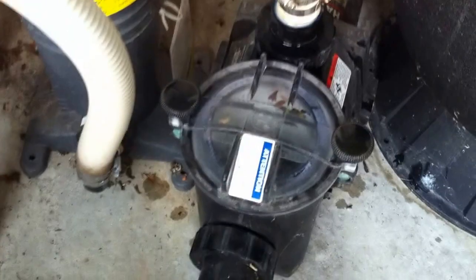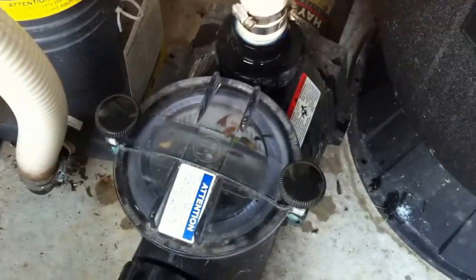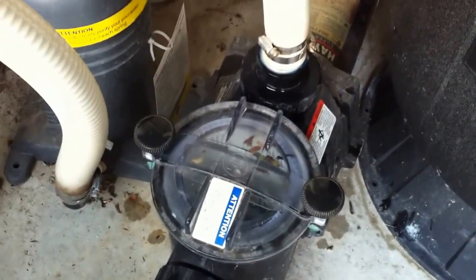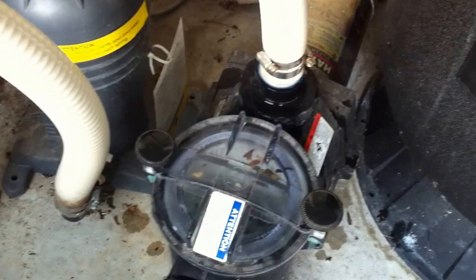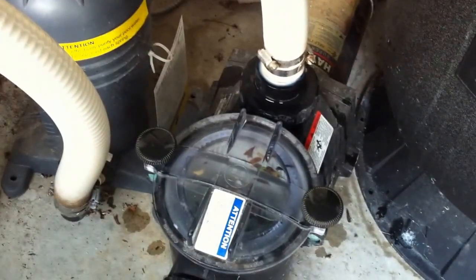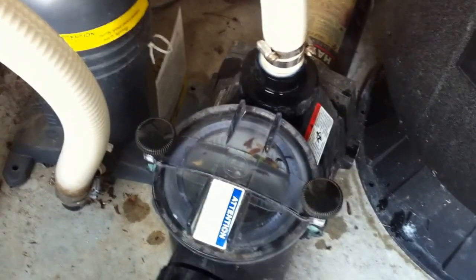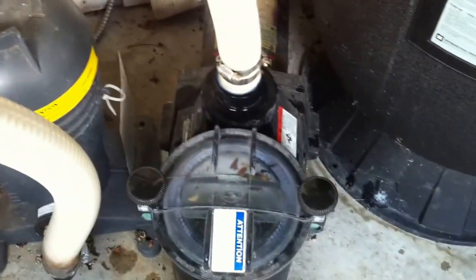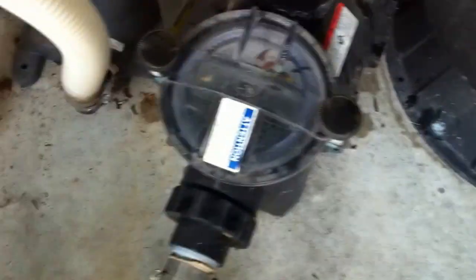Another quick video here on pump installation deficiencies. Starting at the suction line into a Super 2 — this is a Hayward Super Pump 2, a high head application pump made for lots of flow. Things like a lift to your third story solar, a waterfall, or a hot tub with 10 jets that you need to run. That's what that pump is made for, indicated by the round chamber on the basket there on the wet end.